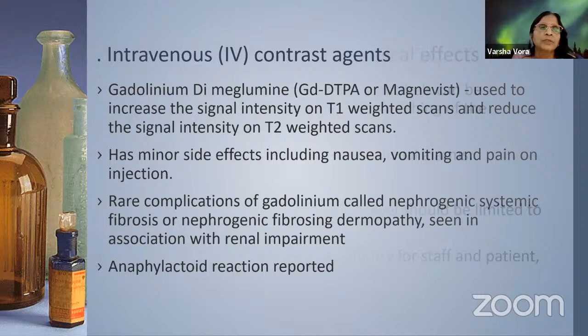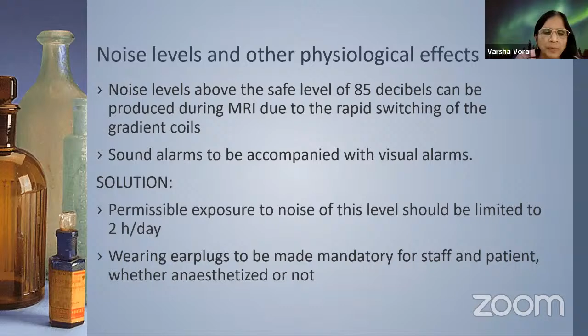Noise levels and other physiological effects. Noise levels above the safe level of 85 decibels can be produced during MRI due to the rapid switching of the gradient coils. Sound alarm to be accompanied with visual alarm. Solution: permissible exposure to noise of this level should be limited to 2 hours per day. Wearing earplugs to be made mandatory for staff and patient, whether anesthetized or not.